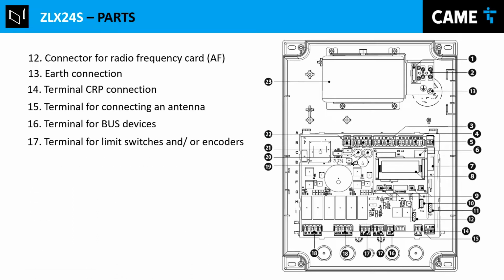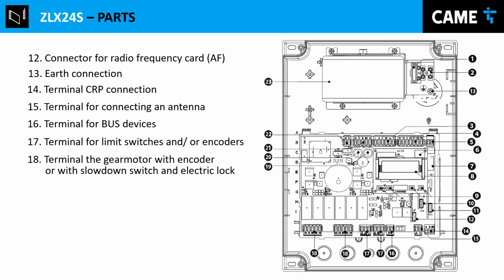Terminal for limit switches - if your operator uses limit switches, you connect them here, depending on whether you have only one operator. I'll show you later how to connect motors and operators. This one is different - it's also where you connect the operator, but this is actually the motor, M2 and N2, which is the one I have here, plus the encoder. This is the axle, so it has 3 cables for that. These are the connectors for the actual motor operator - I'll show you that later.